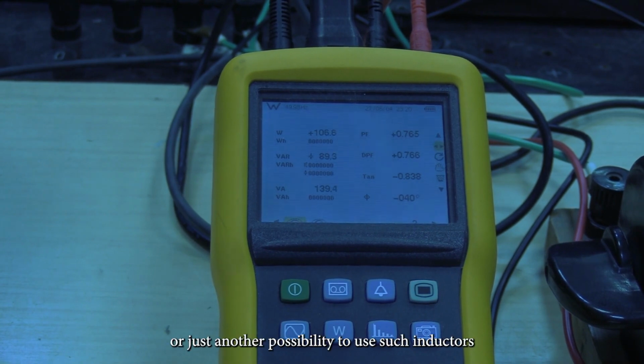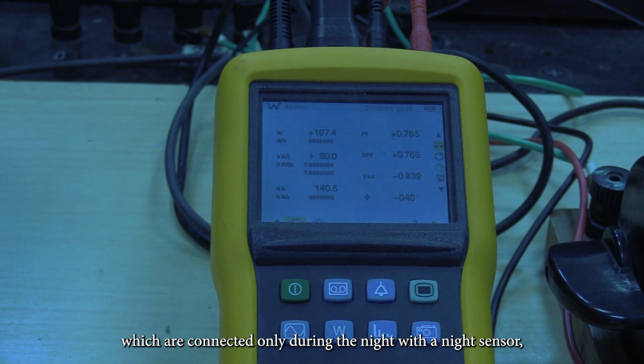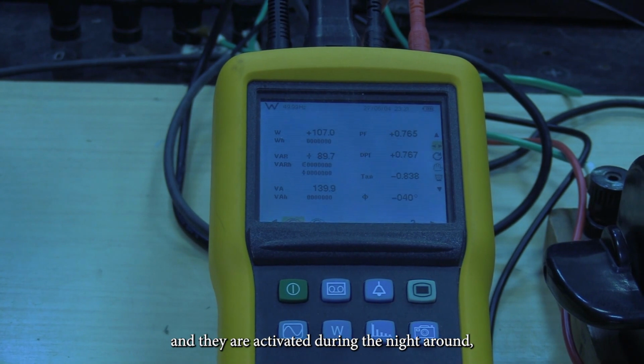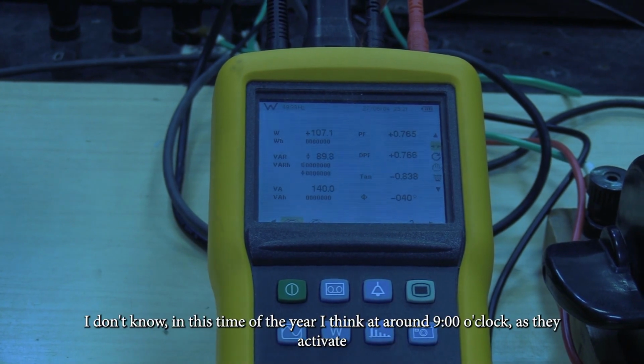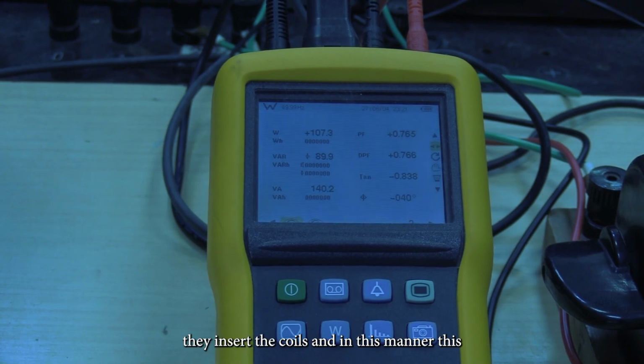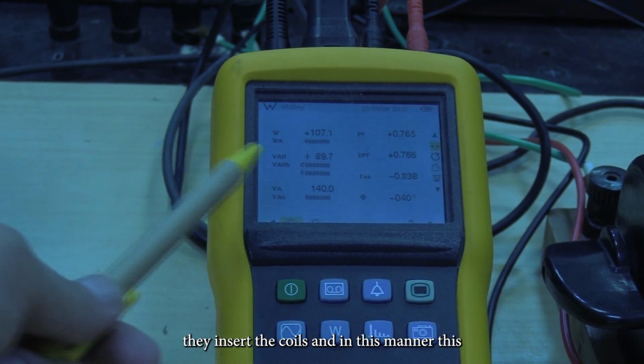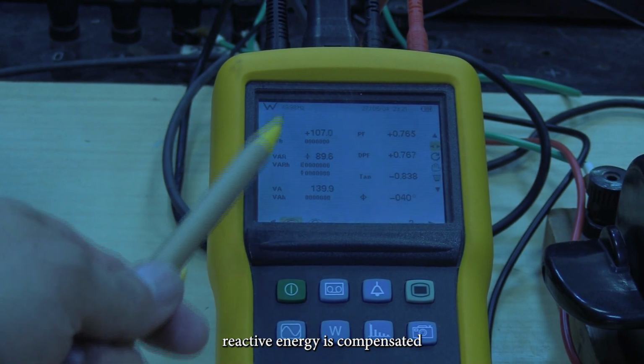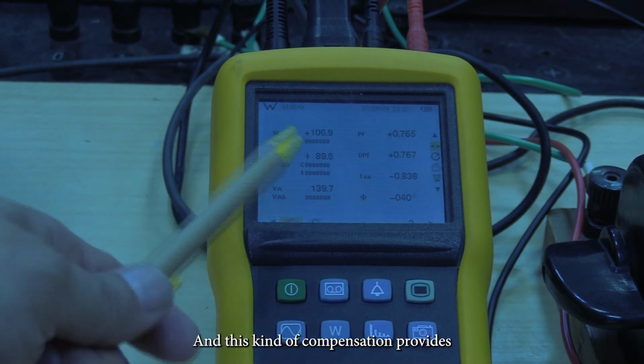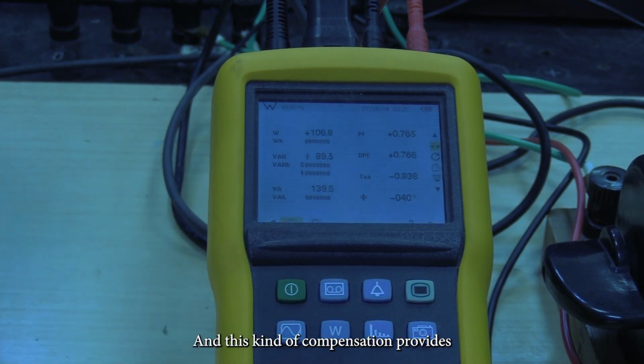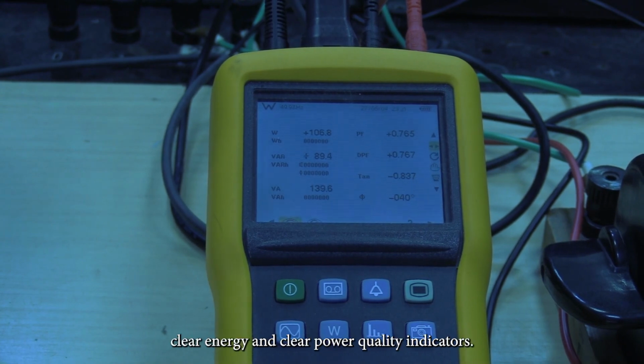Or there's another possibility to use inductors, which are connected only during the night with a night sensor, and they are activated during the night, around, I don't know, in this time of the year, I think around 9 o'clock. They activate, they insert the coils, and in this manner, this capacitive reactive energy is compensated. And this kind of compensation provides us clear energy and clear power quality indicators.